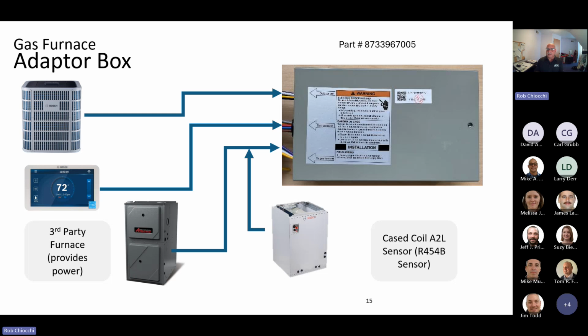You will require this adapter box. One word of caution though, there are no AHRI ratings for the old furnace and the new Bosch A2L product. So if you're going for a 25C tax credit scenario, the old furnace will not have a rating to match with the new A2L equipment. I did check this morning, and we do have some of the new Bosch A2L equipped furnaces in stock to go with the Bosch Ultra heat pumps we have in stock if you would choose to go dual fuel in that scenario.